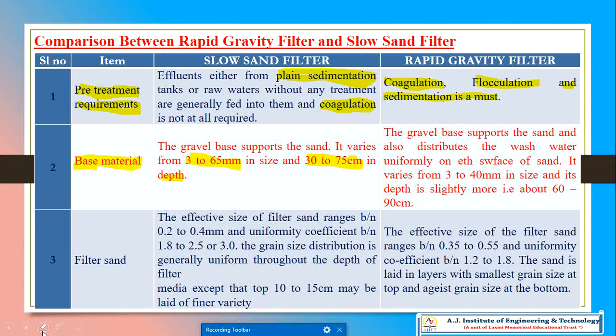For the slow sand filter, the depth is around 30 to 75 centimeters and the particle size is 3 to 65 mm. For the rapid sand filter, the gravel base supports the sand and distributes the wash water uniformly on the surface. The size varies from 3 to 40 mm, and the depth is slightly more than 60 to 90 centimeters. There is no much difference — only variations in depth and size.